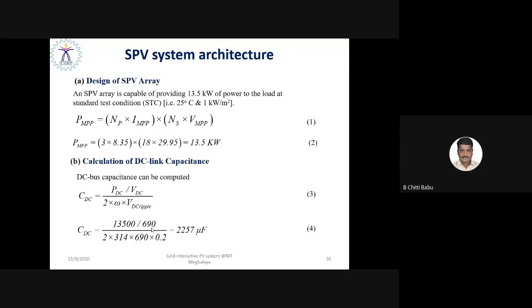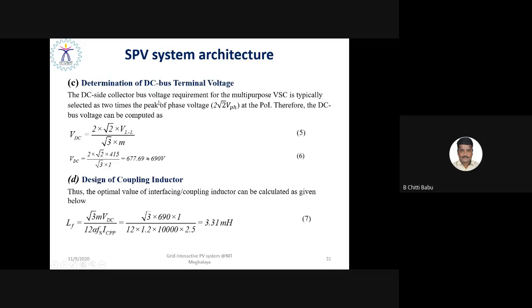So the DC link capacitor has been designed with 2257 microfarad. Assume that the angular frequency is about 50 hertz, that is 314. And the VDC ripple would be around 20% of the rated voltage. And for the determination of the DC bus terminal voltage, as I told you, as you are converting DC into AC, the line to line AC voltage would be around 415 volt three phase, according to our Indian grid standard.